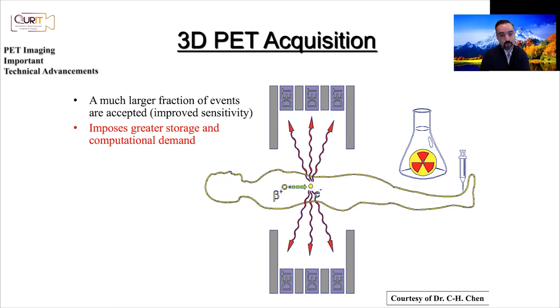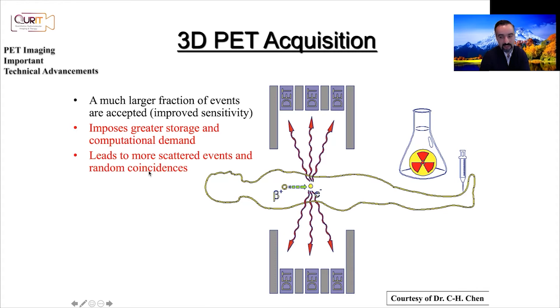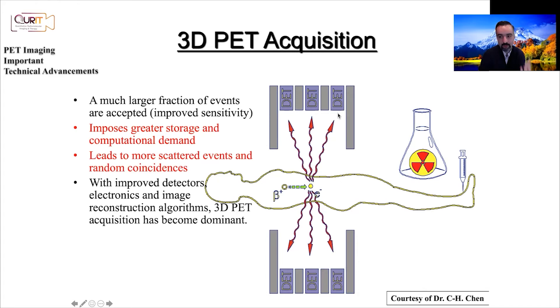With improved detectors, faster electronics, and better reconstruction algorithms that model and correct for scatter and randoms, the field naturally switched to 3D PET acquisition. PET has electronic collimation through coincidence detection, so there is no need for physical septa between rings. Vendors have primarily switched to 3D PET acquisition, and sensitivity has increased significantly as a result.